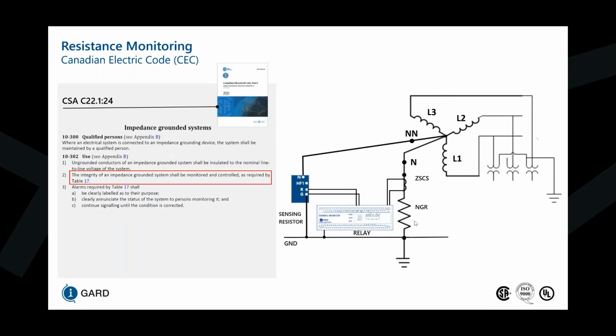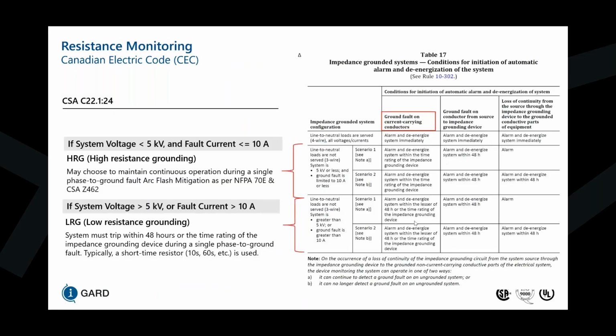So we've already discussed table 17, but I like to mention that typically row 2 is dictating for high resistance grounding, where your system voltage is less than 5 kV and fault current is less than or equal to 10 amps. And then row 3 is typically reserved for low resistance grounding if your system voltage is greater than 5 kV or fault current is greater than 10 amps.